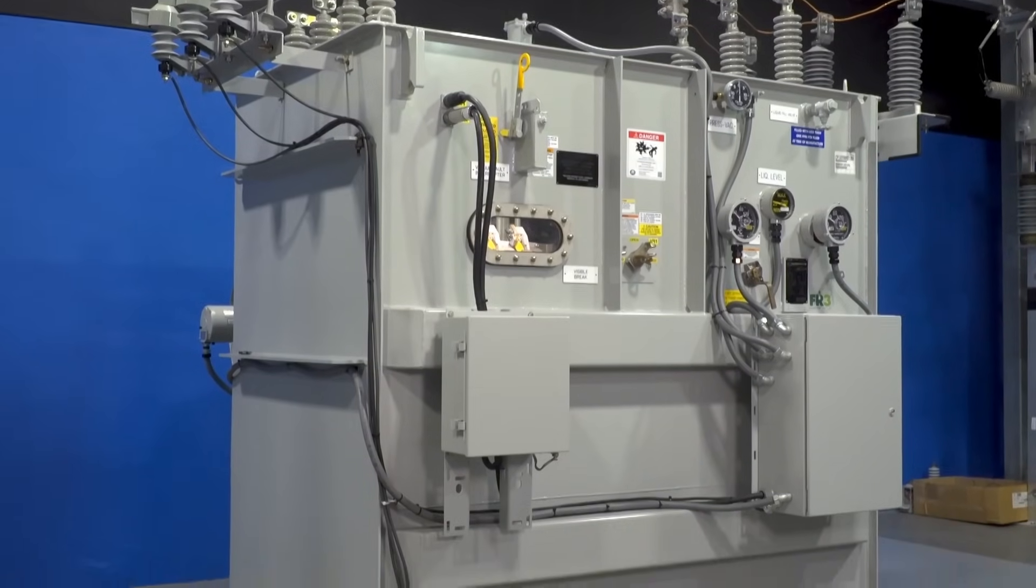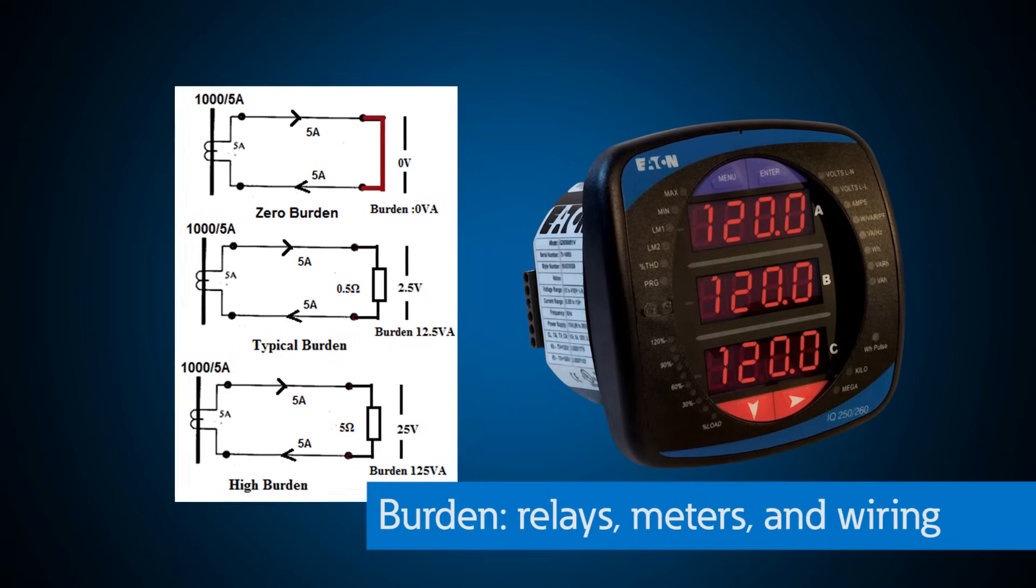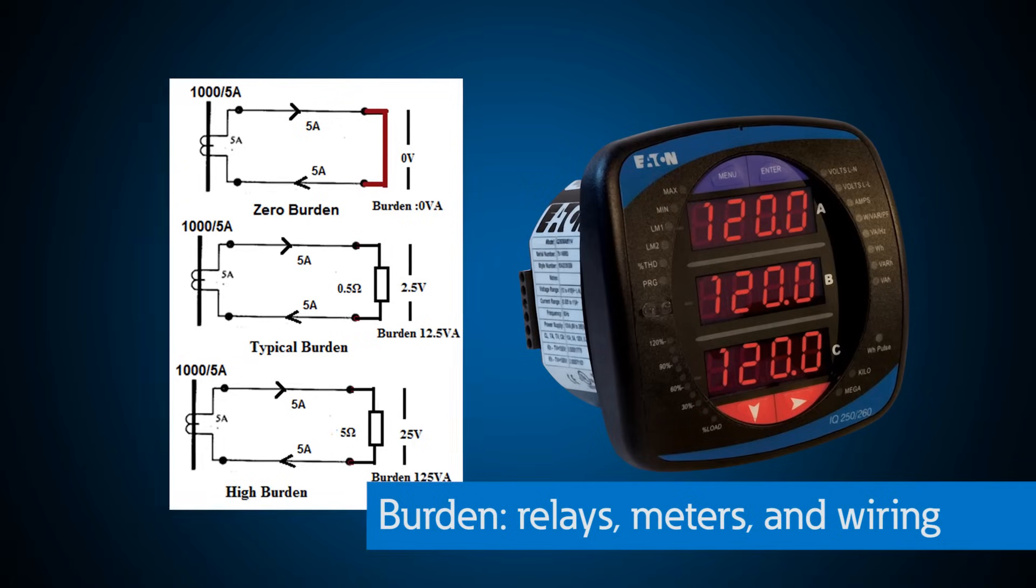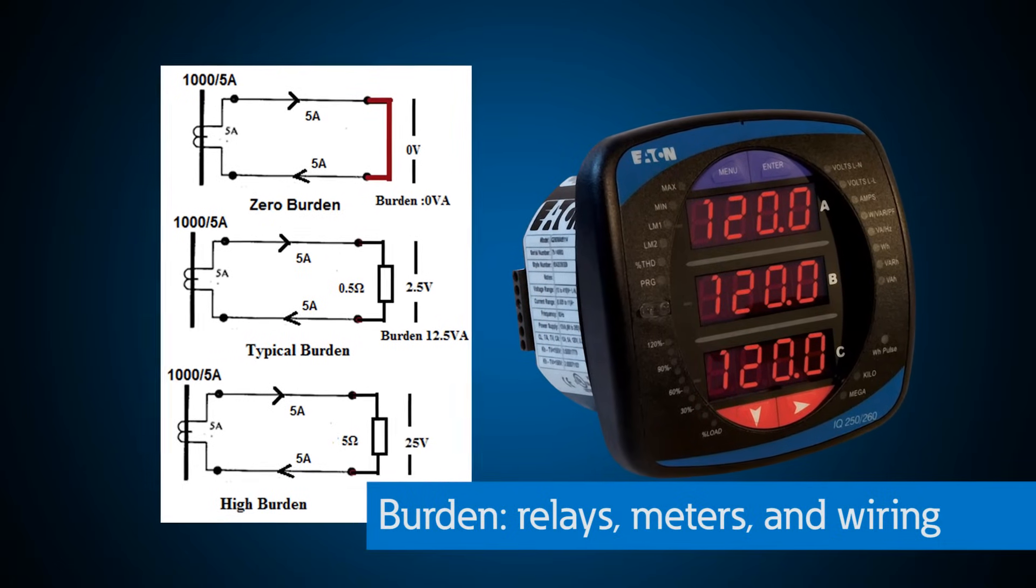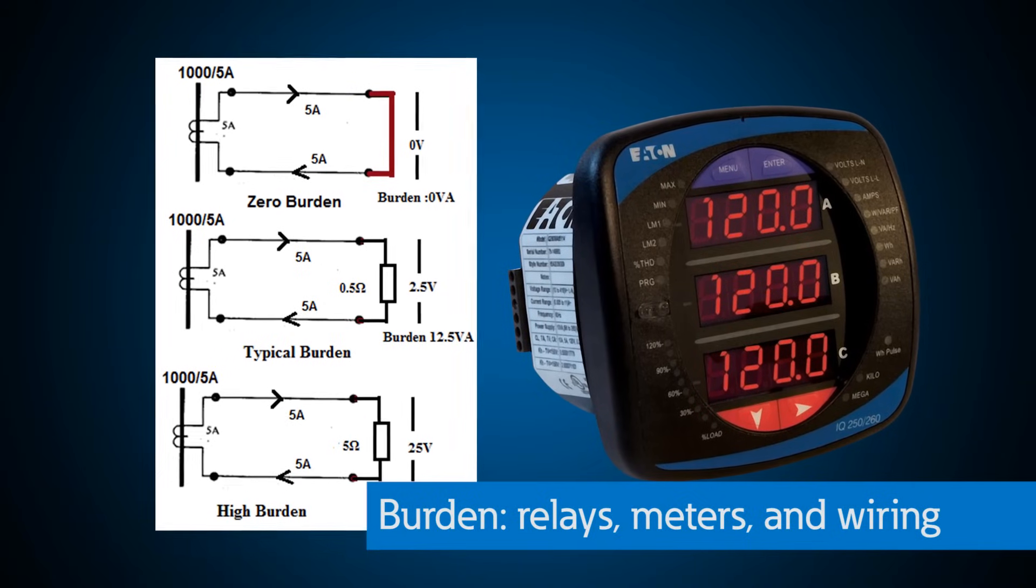Like all transformers, CTs have volt ampere or capacity ratings. CTs have limits to the number of devices and length of wire that can be connected to its secondary side, which is called the burden. Items that contribute to burden are relays, meters, and wiring. The best way to reduce burden is to keep the conductors between the CT and the metering devices as short as possible or increase the wire size to reduce resistance. The burden for today's modern electronic relaying and metering is very low compared to older equipment, but care must be taken to ensure CTs are not overloaded or inaccurate current measurements or protection will result.